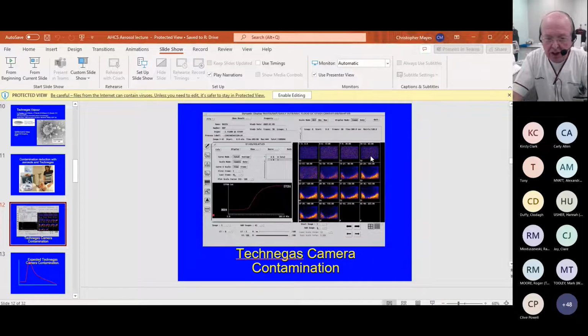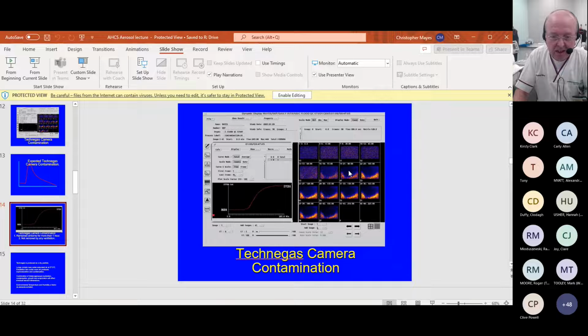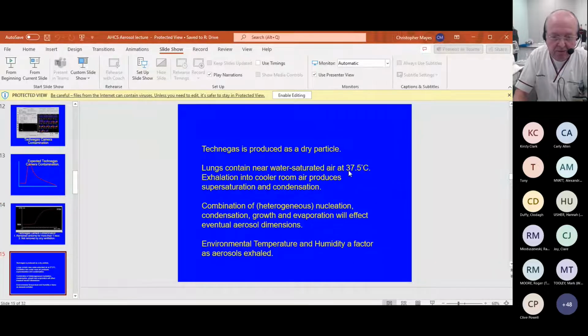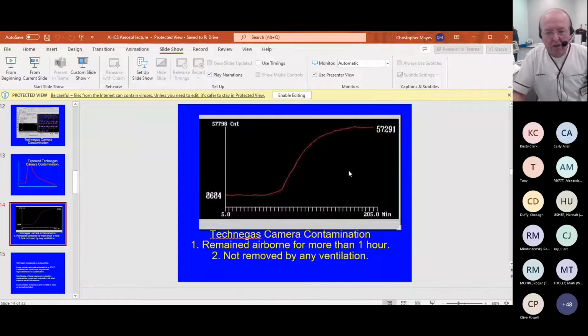Now, as soon as I did the contamination, it started to build up in the gamma camera, and we start to see the triangles that were appearing on my bone scans. So I demonstrated where these triangles had come from, and what was happening here, as I say, is that the radioactivity was being sucked by cooling fans behind all the radiation shielding to get picked up by the electronics that the fans were cooling, and that was what we were seeing. So that was the pictures, but the graph really confused me, because this was not what I was expecting.